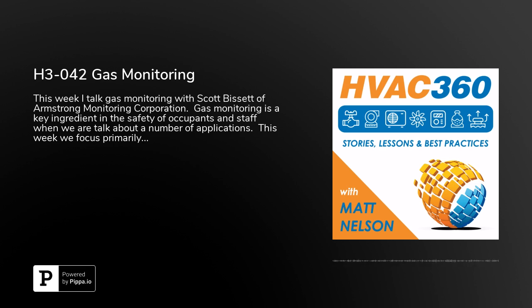Okay. Now, does it matter if it's 410A or 132? I mean, as far as different refrigerant types go, you still want it mounted down towards the floor. For most common commercial refrigerants, yes. The only major exception to that rule would be ammonia. Ammonia tends to evaporate very quickly, and it is lighter than air. So when we're dealing with ammonia chiller plants, whether it's arenas or other applications, we tend to recommend having the sensor up high.